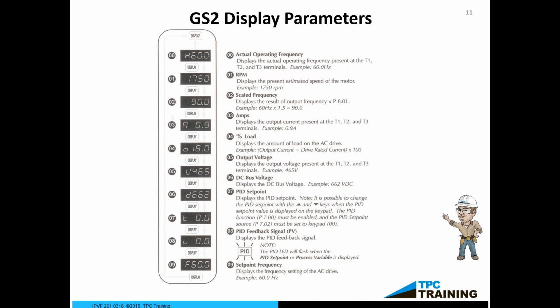On the display, you'll see all the little bits of information that you can pick off of this thing. You've got the actual operating frequency. And unfortunately, if you notice number 7 down there, it says PID set point. Unfortunately, with most of these displays, and I'm going to say 80% of them, it's not going to be plain language. You're going to have different addresses with different nomenclature on there. It's going to say U's and T's and Z's and different numbers, and that has to do with memory storage. So just going through the display is very, very helpful.